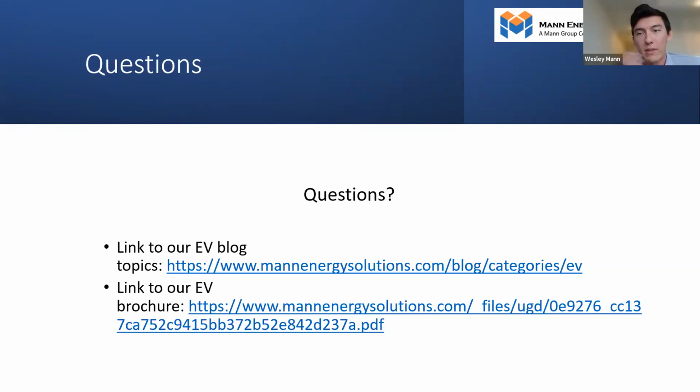Like what I was talking about, that's more for when you have individual tenants looking for their own charger. When we're talking about multiple tenants sharing a charger, or some kind of visitor parking situation, that's when you potentially want to go with an OCPP system, where you have a smart charger, which is pay as you go, and that's just communicating directly with cloud client software, which will handle all the billing.